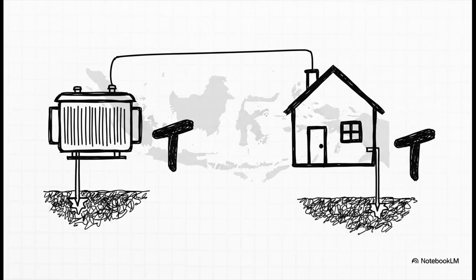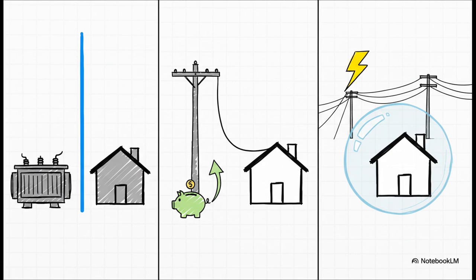So here's the crucial point for us. For residential customers here in Indonesia, the standard mandated by the state utility, PLN, is the TT system. The first T means PLN's transformer is grounded, and the second T means your house has its own separate connection to the ground. This wasn't some random choice, it's actually very strategic. It creates a clear line of responsibility between PLN and you, the homeowner, and it saves a ton on infrastructure costs because PLN doesn't have to run an extra protective ground wire to every single house.